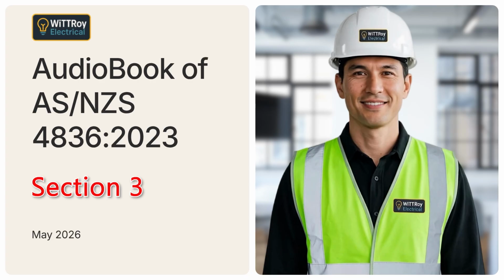Suitable PPE must be used when attaching or removing temporary bonding conductors. PPE means personal protective equipment. The safety idea is that temporary bonding helps control unexpected voltage, induced voltage, or accidental re-energization risk at the worksite.